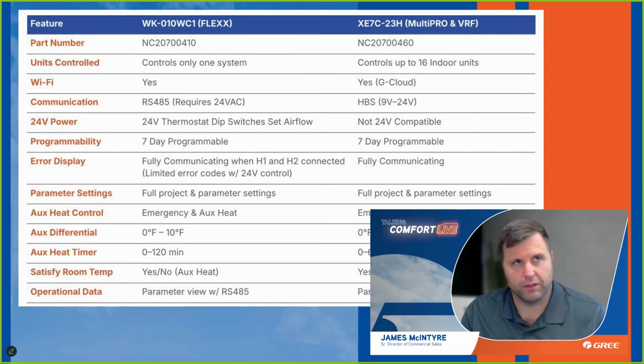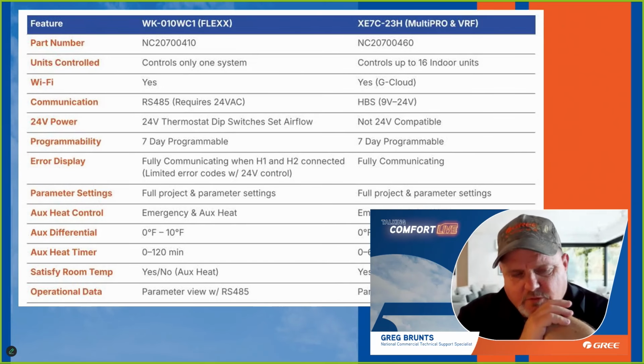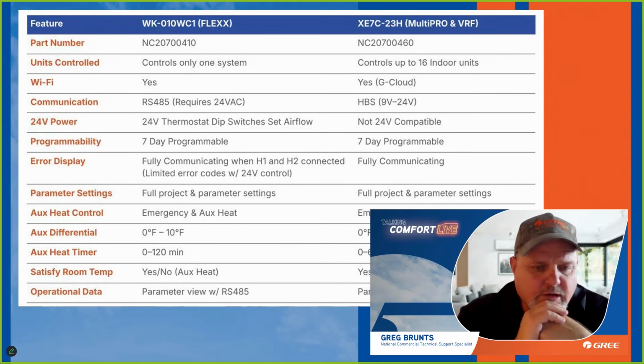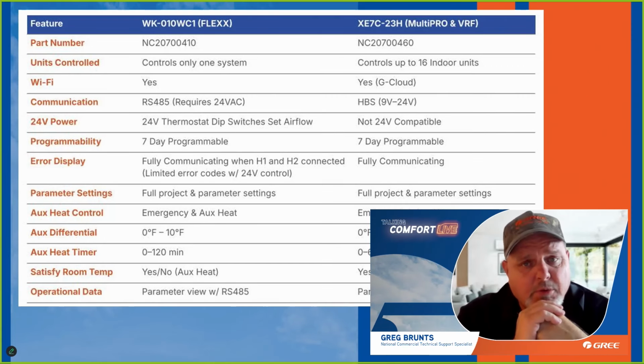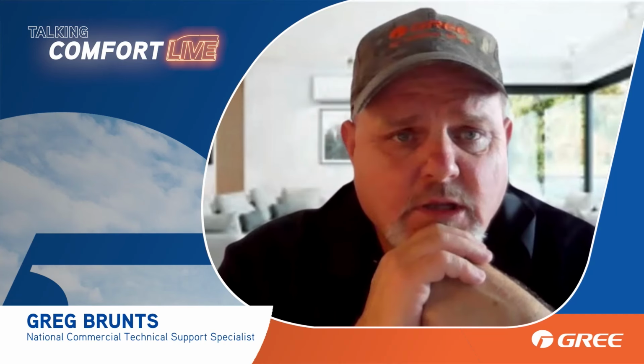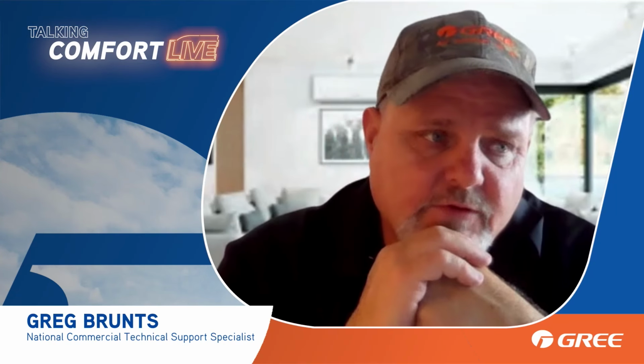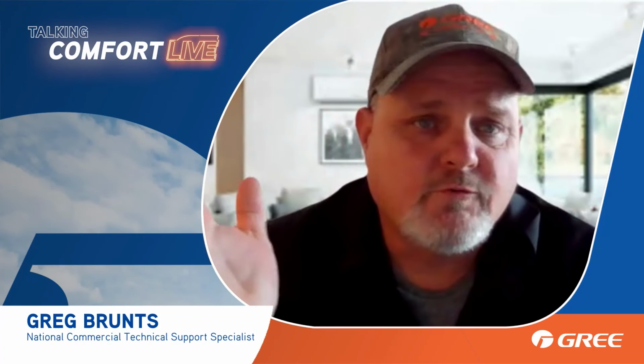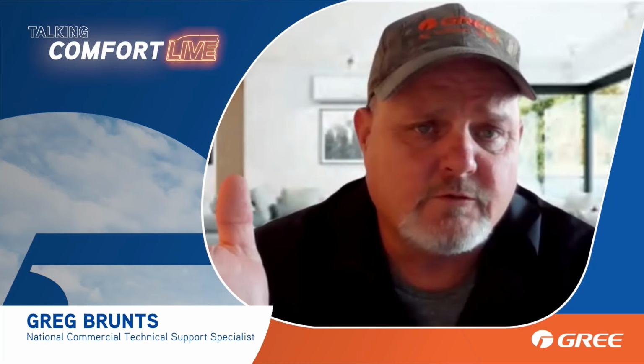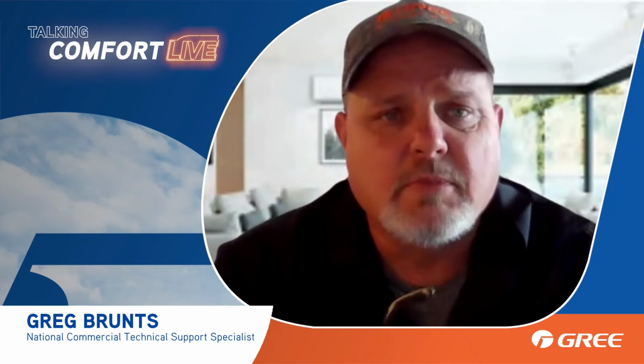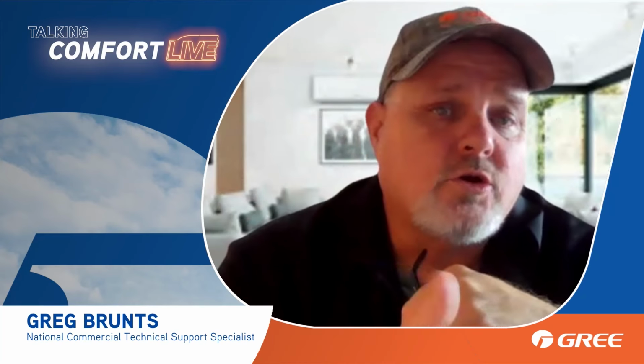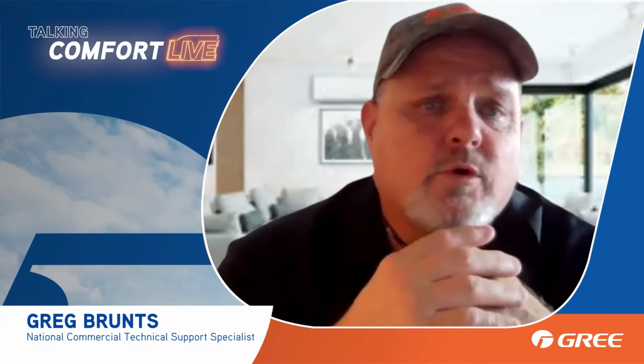So running the outdoor and indoor on 24 volts, but using the wired controller. Okay. And then also, we haven't launched it yet, but once it comes, we are going to have the service tool for the GREE FLEXX R32 units. But if you don't have H1, H2 hooked up, then you can't see the whole system. You've got to plug in for both. You can plug into the indoor unit and see that unit, and you can plug into the outdoor unit and see that unit. But if you have H1, H2 wired between the two units, whether you're using 24 volt or not, you can still use the service tool, but control it by 24 volts. It's just whether or not you're hooking up H1 and H2 to the controller to use RS-485 to control the unit.